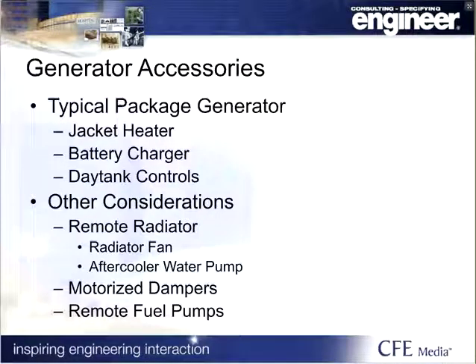Items to consider while designing the generator system are ancillary equipment that supports the operation of the generator. A standard package generator will normally require connections from the EPSS to power the jacket water heater, battery charger, and fuel system controls. The jacket water heater ensures the generator maintains a minimum coolant temperature to ensure a 10-second startup and sync. The battery charger maintains a fully charged starter battery. Other items to consider depending on the type of generator installed may be remote coolant systems if the EPS is installed indoors and adequate ventilation is not achievable.